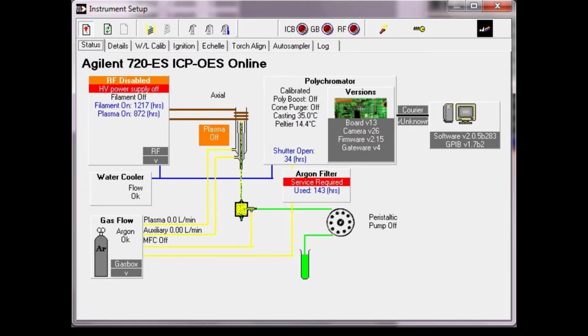This is normal. The water cooler flow is okay, and the gas flow is good. If not, you'd see these sections highlighted in red as well, and will need to correct the problem. The argon filter says that service is required, but don't believe it. The software has an error that will not allow this message to be reset, so it's okay to ignore. The Peltier is at room temperature, and as soon as we reach the 20-minute mark, it will reduce quickly to -35 Celsius. I'll discuss that more later.